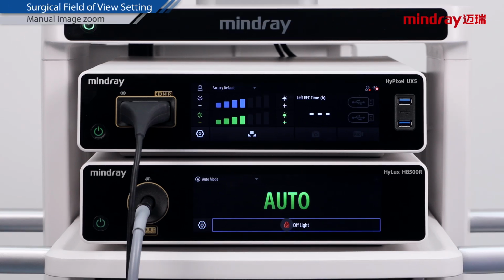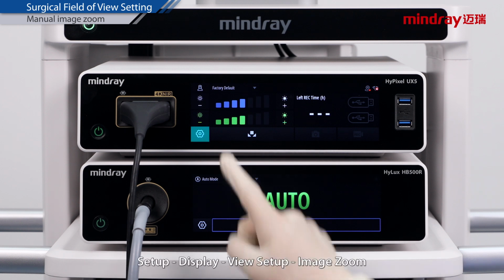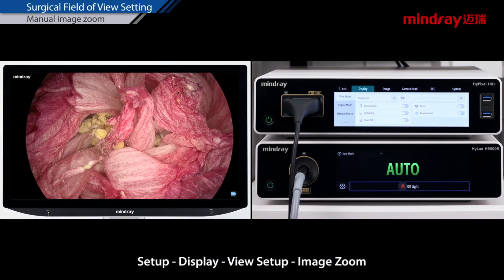Manual Image Zoom. UX5 can also manually zoom in or zoom out the surgical image. The manufacturer recommends not zooming in the image and uses the 1.0x original image. If the application scene needs to be zoomed in, it is recommended to use 1.2x. A larger magnification factor will reduce the image definition. Operation path: Setup, Display, View Setup, Image Zoom.